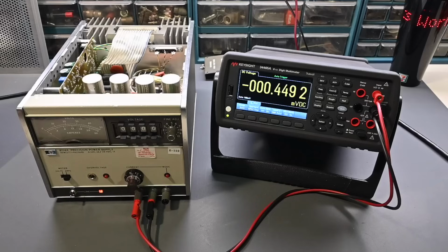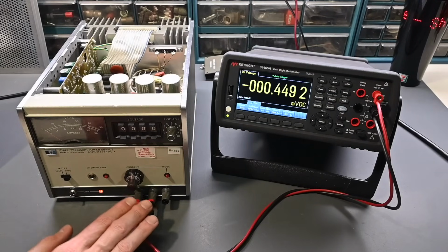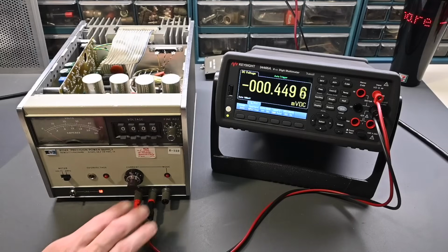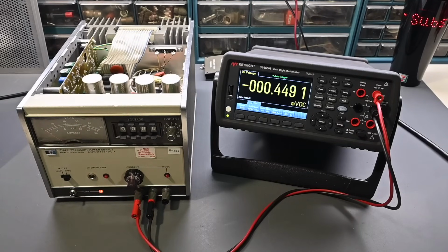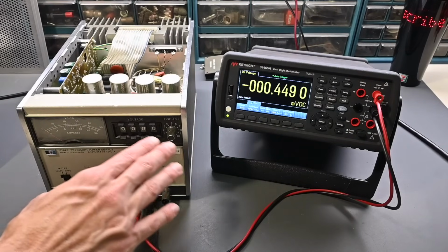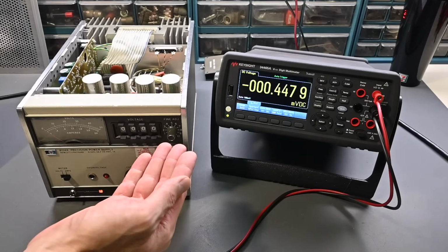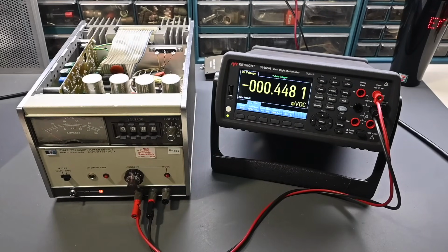And then moving on through some more adjustments and calibrations, they have you do the 0 output voltage adjust. And I had noticed that this was not sitting at 0 volts when this was all right at 0, and the output was floating up to a value a little bit higher, and it was kind of throwing off some of the fine adjustments over here, which should be just in 1 millivolt steps. It really was off by more than you'd want to see.